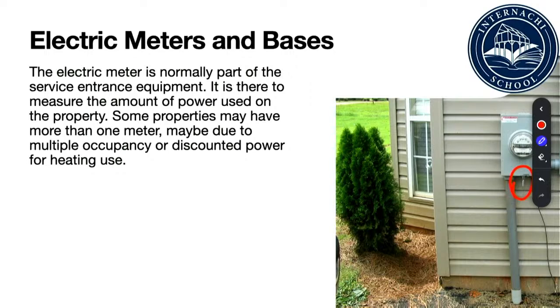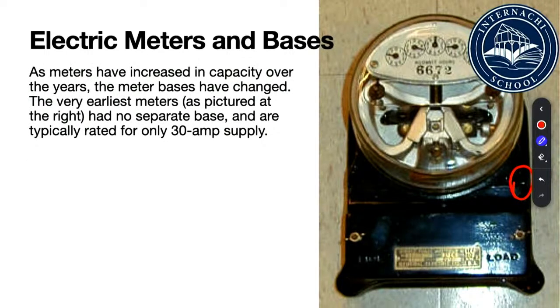But what they didn't do was upgrade the service entrance cables. They did not upgrade the conduit that's coming in here. They did not upgrade the meter panel, and they didn't even cut any of those tamper tags, so they couldn't get in there to change the wiring in the first place. So we may have actually made a problem worse when I start thinking about this, because if you end up putting a meter panel inside the house that's rated for 200 amps, but you're only feeding it with wires that are rated for 100 amps, you're going to allow 200 amps to flow through something that's not designed to carry 200 amps. So knowing all the things that have different ratings on it, to me, is important. And figuring out these 5 things to see if something's safe is also an important thing. So this is just something out of the old history books right here. These round meter bases, and again, we're talking about the panel, not the actual meter itself, all right?